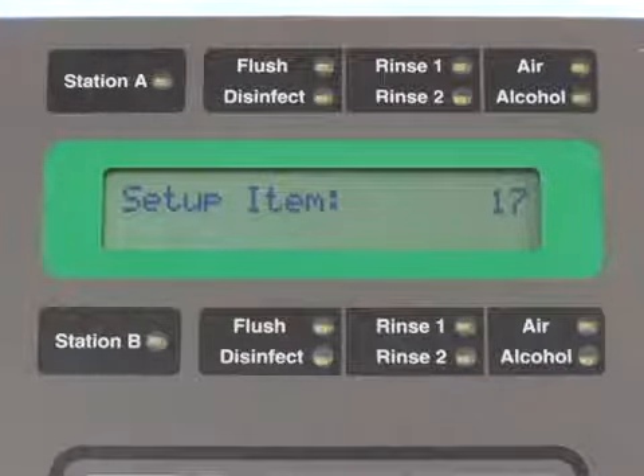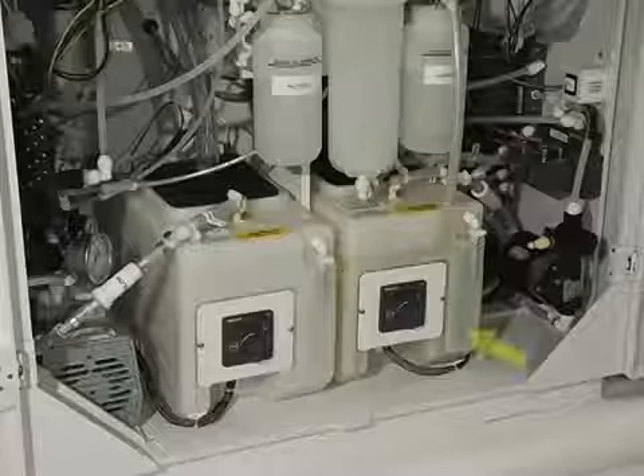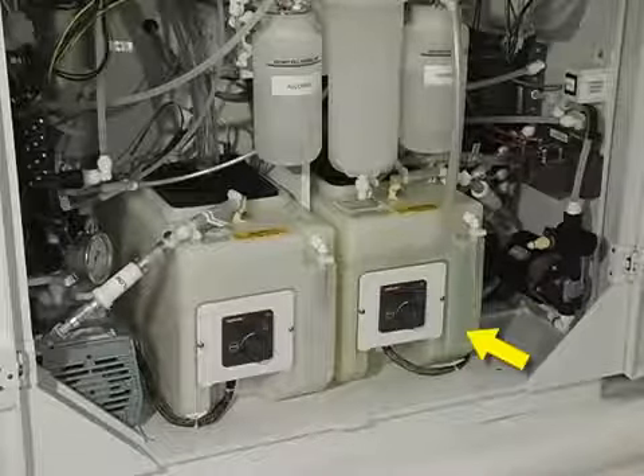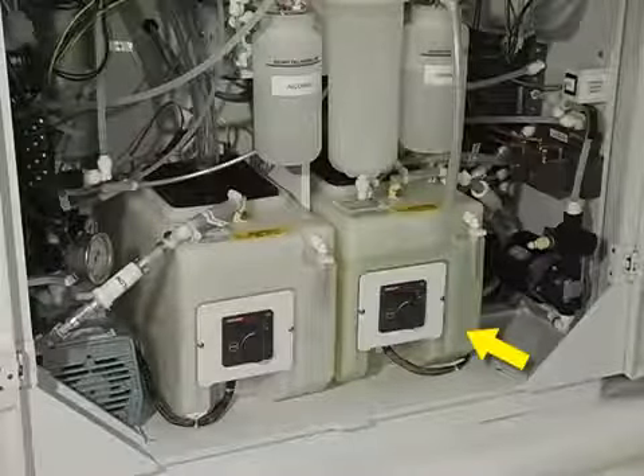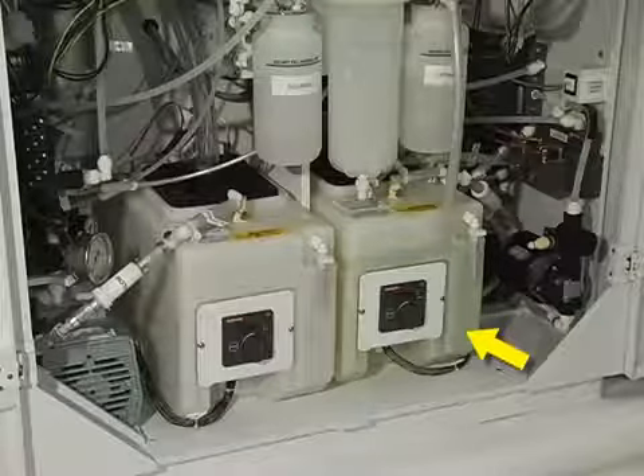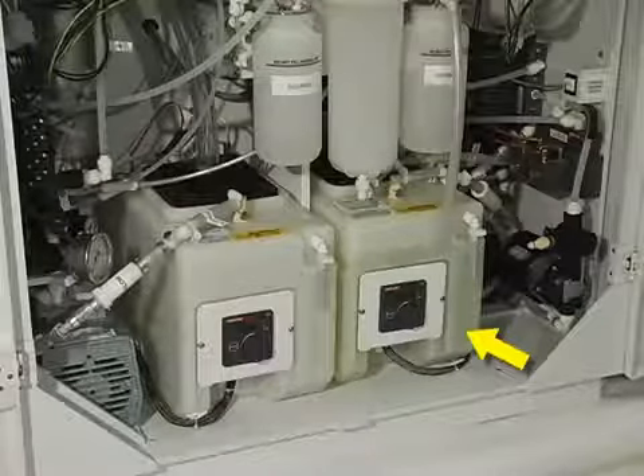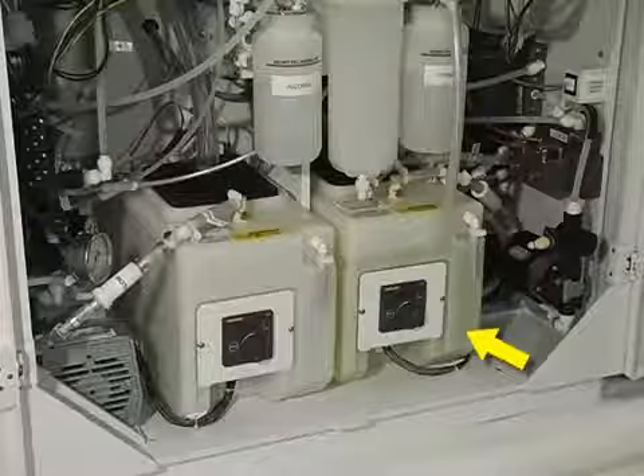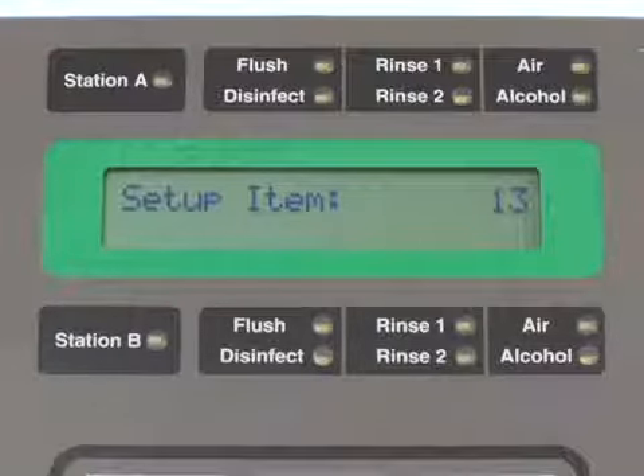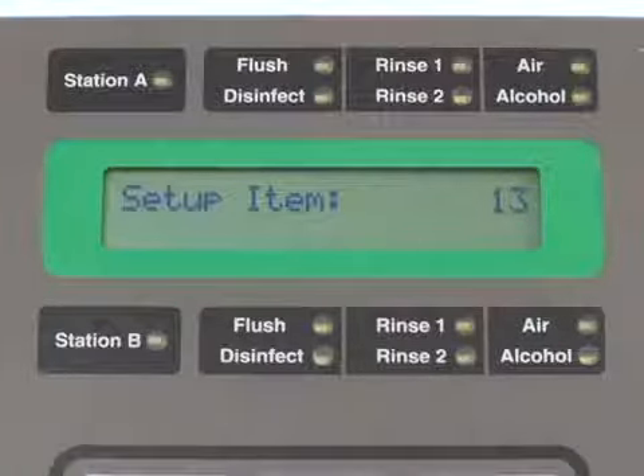After the cycle is complete, a message will print out. At this time, proceed to add approximately 1 gallon of disinfectant to the Station B reservoir to complete the water line treatment. If using a heated disinfectant, allow it to heat to the appropriate temperature, which can be verified by entering Setup Function 13 and viewing the display.